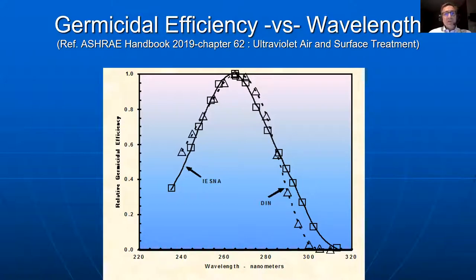Here's a reproduction of what you find in the ASHRAE handbook, 2019, chapter 62, which deals with ultraviolet air and surface treatment. If you look at the wavelength on the abscissa of the graph, 265 is about the peak of germicidal efficiency. UV lamps using mercury are around 254, which is about 85% efficiency. So it's a very useful method, you're hitting almost at the maximum of that curve.